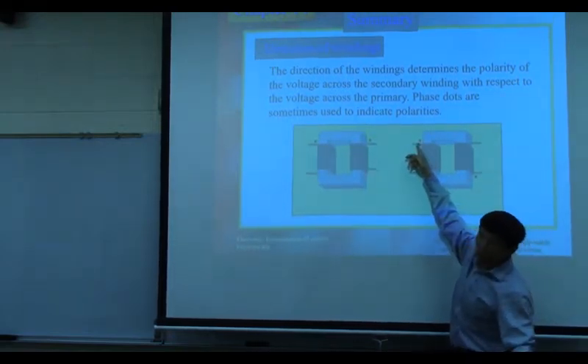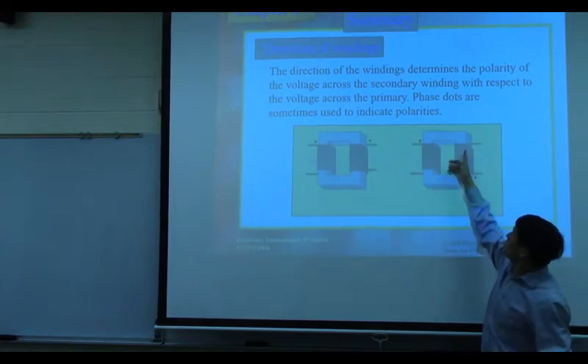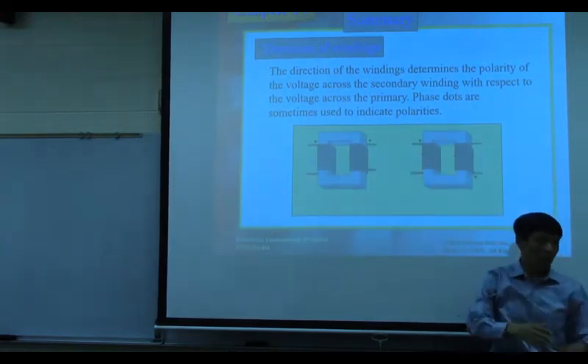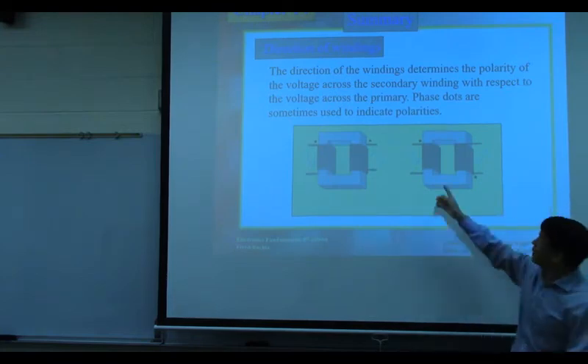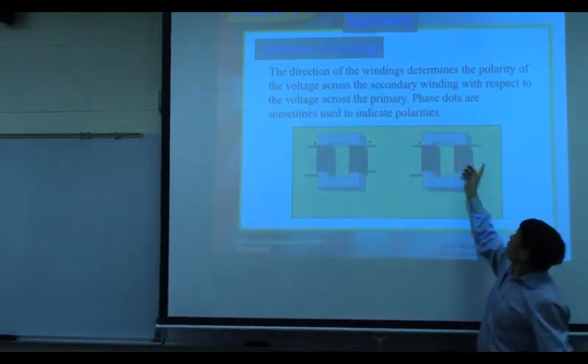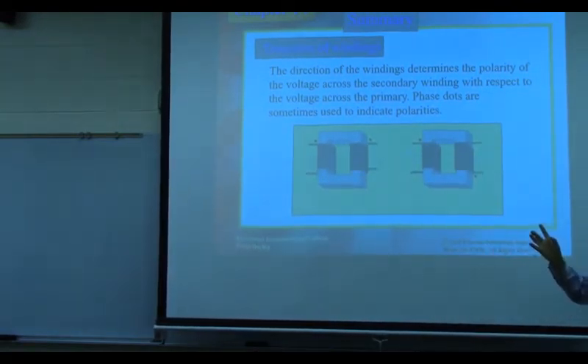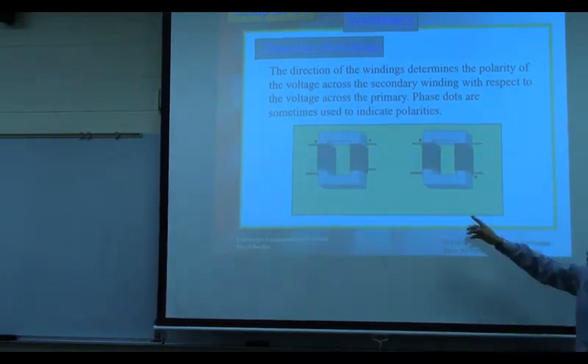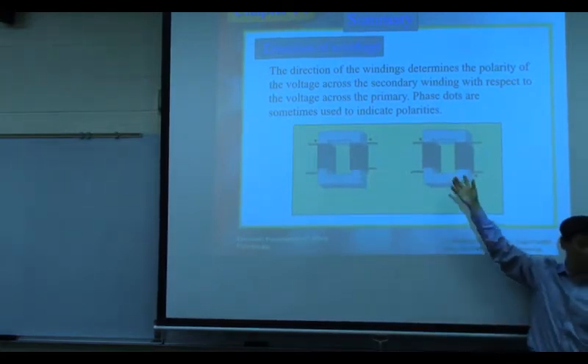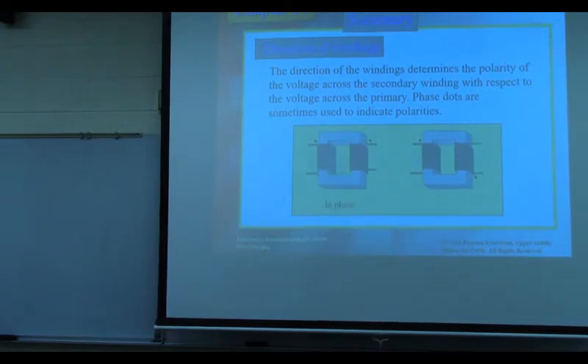In another configuration, the dot mark on one terminal and the absence on the corresponding terminal means those two points are out of phase — that is, 180 degrees out of phase. If one goes up, the other goes down. When using a transformer, you need to look at the dot markings to determine whether you want in-phase or out-of-phase voltage, and connect accordingly.